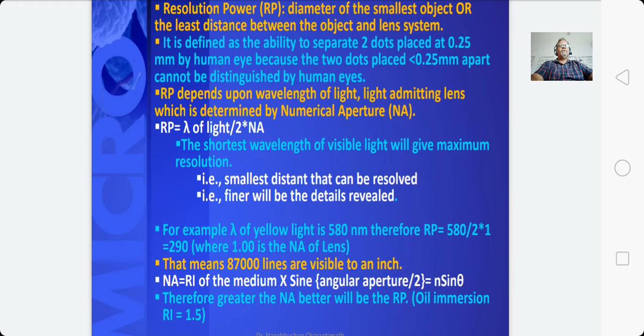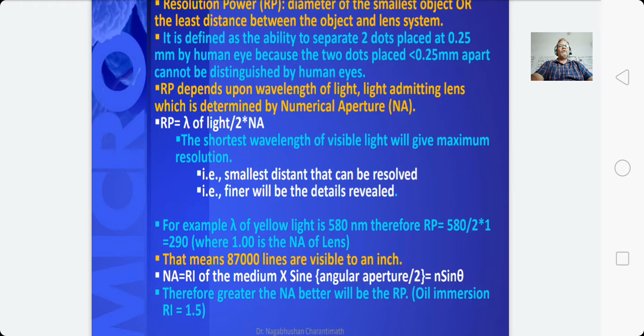Numerical aperture is the refractive index of the medium multiplied by sine of the angular aperture divided by 2, that equals n sin θ. Therefore, the greater the numerical aperture, the better the resolution power. That is why we make use of immersion oil when we want to magnify the compound microscope images to about 1000 times or 2000 times, where the refractive index of the oil is 1.5 rather than 1.